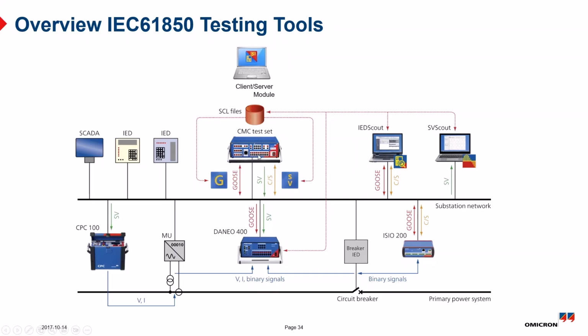Instead of pushing voltage and currents and measuring binary inputs and outputs on the front, we plug in an Ethernet plug, and we can push sample value streams. We use our same software, same everything, but instead of pushing analog values out the front, it's pushing sample values out the back. And then we measure GOOSE. We provide a stimulus to the relay. When the relay responds with a GOOSE message, we can read that GOOSE message and grade that relay response just like we did in the old days. So that part of it still works the same way. It's just the channel is different.